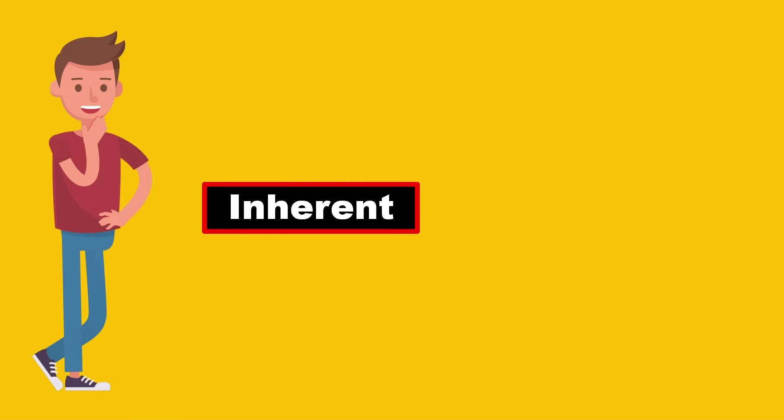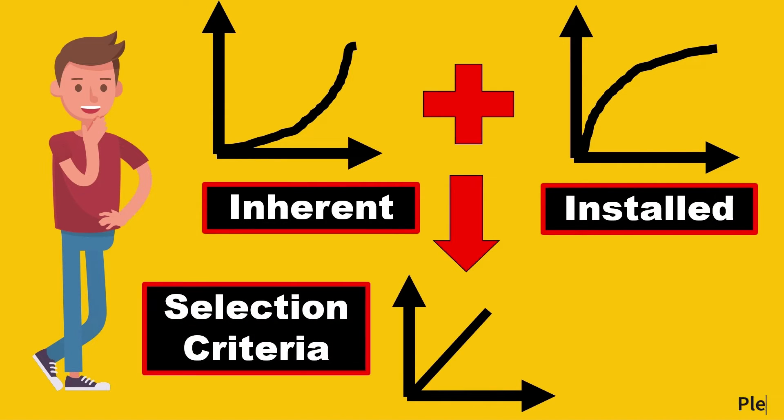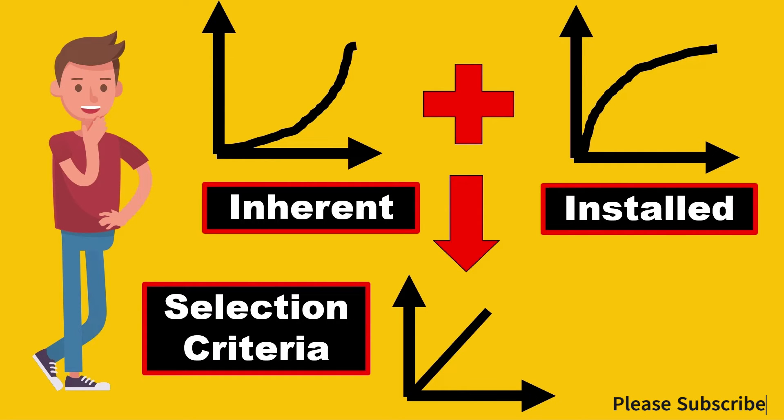You can't change what happens inside the plant, but you can modify the inherent characteristics of the valve. If you modify the inherent characteristics so that when it's finally installed in the plant, the combined output is a linear curve, this is where the engineering criteria of selecting the right characteristics comes in.